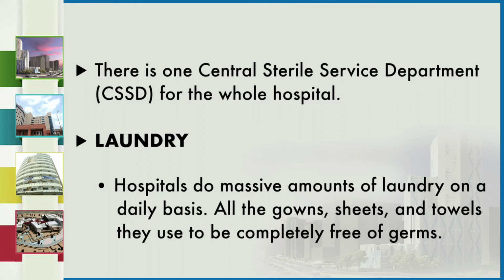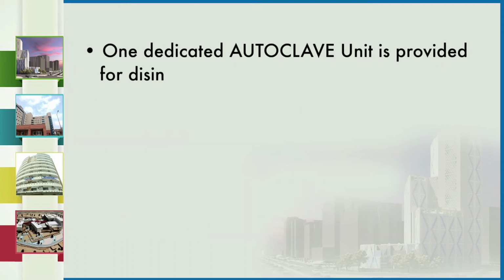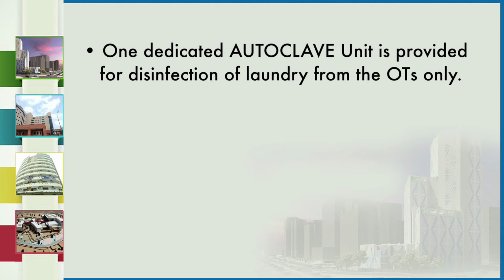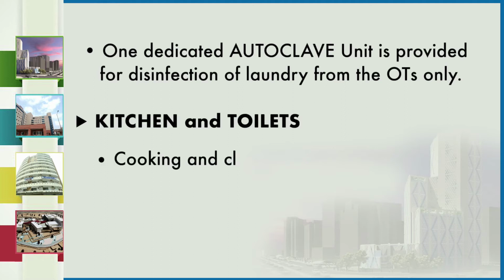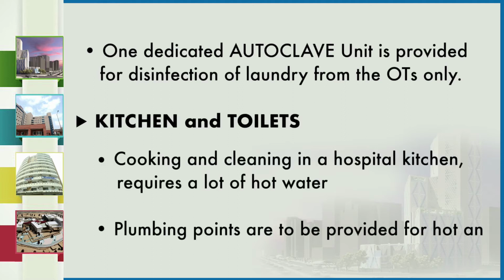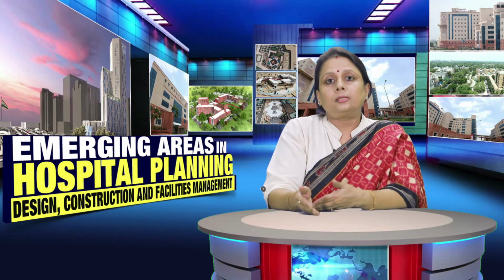All the gowns, sheets and towels they use need to be completely free of germs. So one dedicated autoclave unit is provided for disinfection of laundry from the operation theatres only, and the rest of the hospital is separate. Kitchen and toilets. Now cooking and cleaning in a hospital kitchen requires a lot of hot water, and so do toilets. So accordingly, plumbing points are to be provided for hot and cold water in all the zones where hot and cold water are both needed.